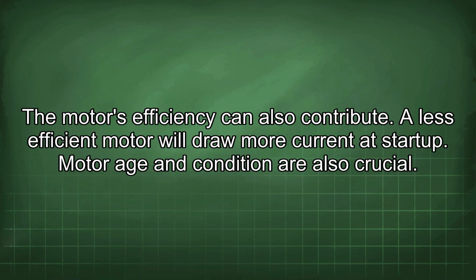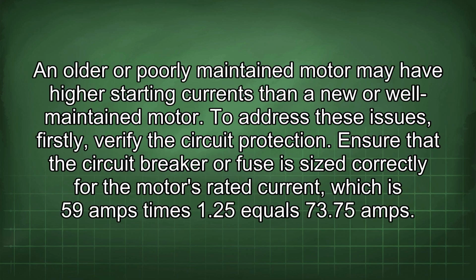The motor's efficiency can also contribute. A less efficient motor will draw more current at startup. Motor age and condition are also crucial. An older or poorly maintained motor may have higher starting currents than a new or well-maintained motor.